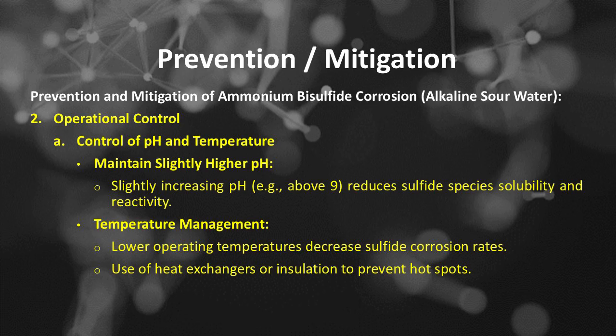Number 2 is operational control, which includes, number A, control of pH and temperature. Maintain a slightly higher pH; slightly increasing pH, such as above 9, reduces sulfide species solubility and reactivity. Control and manage the temperature, as lower operating temperatures decrease sulfide corrosion rates. Use heat exchangers or insulation to prevent hot spots.